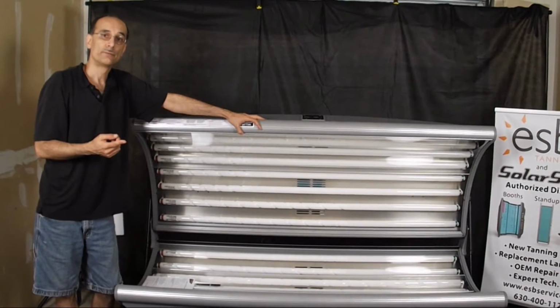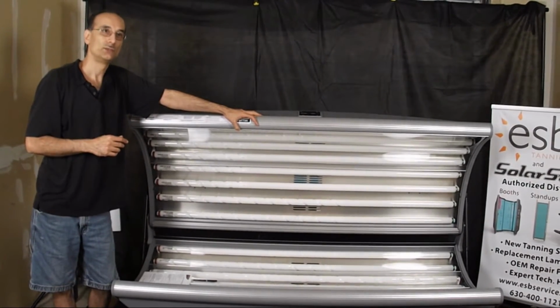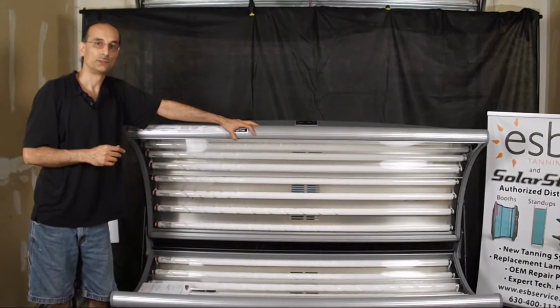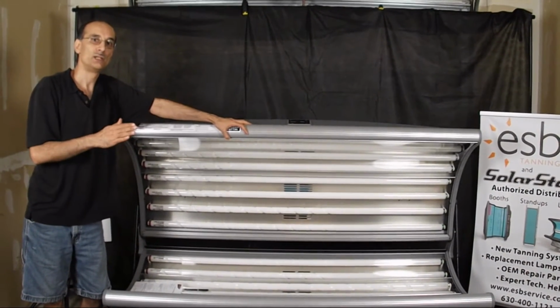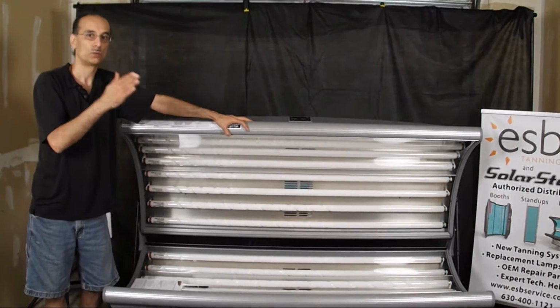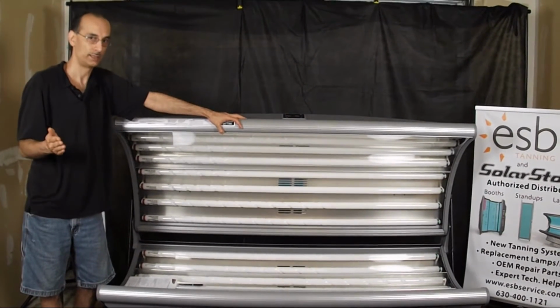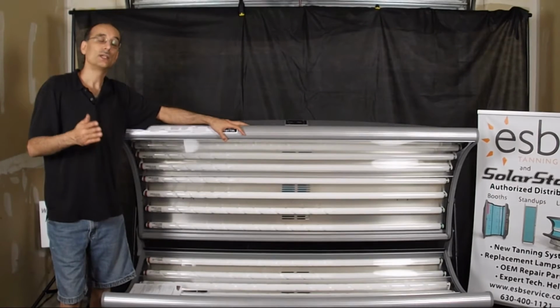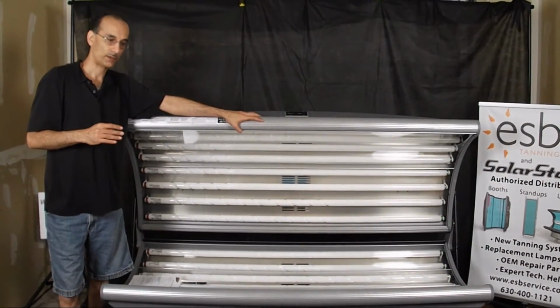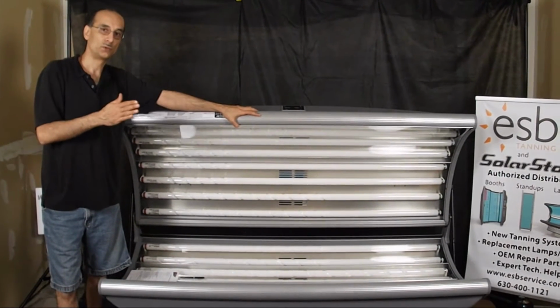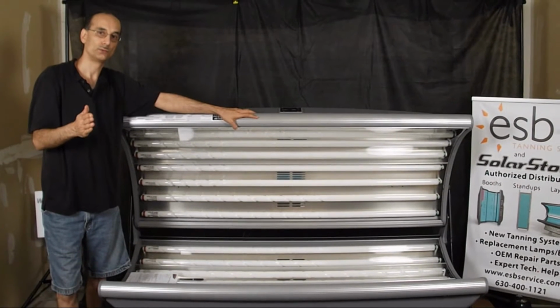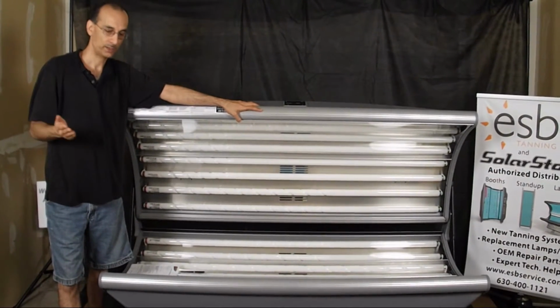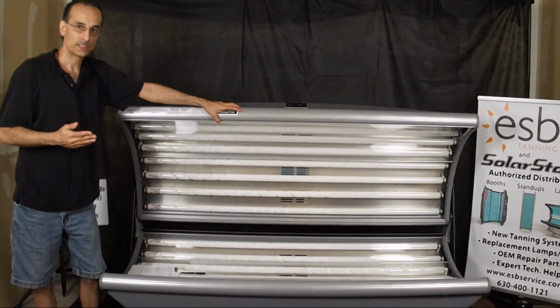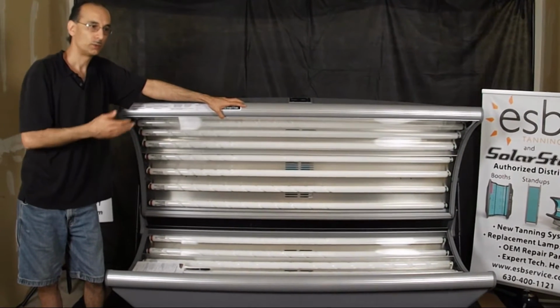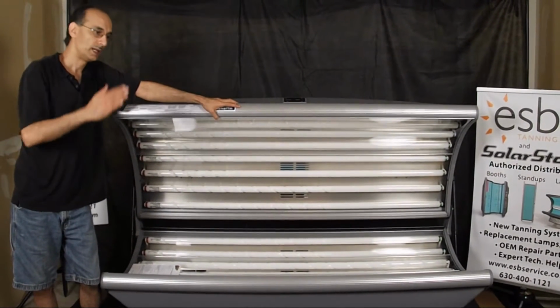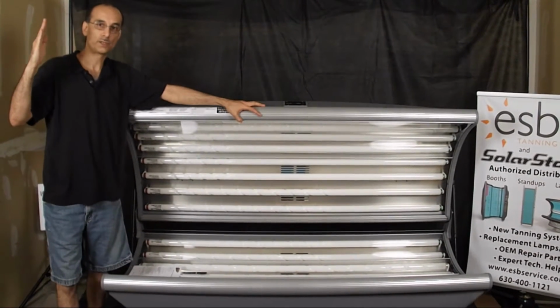On a 110 volt bed, especially older ESB tanning beds, meaning before mid-2000s, the 110 volt bed would be specified to run on 110 to 120 volts, no lower and no higher than that. For the 220 beds, especially the older beds again before 2005, the 220 beds would be specified to run on receptacle voltage of 220 to 230 volts. Again, no lower than that and no higher than that. So if you have a 110 volt bed and you check your receptacle and your receptacle says 115, you're just fine. If it's down as low as 110 or up as high as 120, you're just fine.